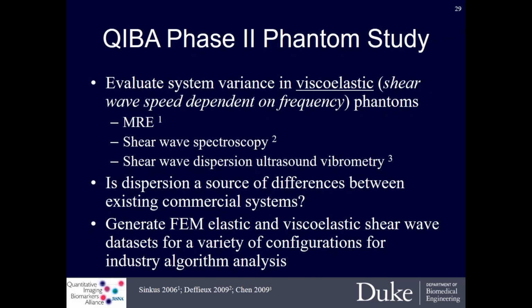One of the confounders is actually the experimental protocol, where coupling the transducer to the flat surface of a phantom required a water path, which actually led to some geometric distortion of the tracking beams and led to some of that bias. Some controlled studies done afterward were able to show that we could reduce some of that focal depth bias but not get rid of it completely, so it remained on the radar as a potential confounder.